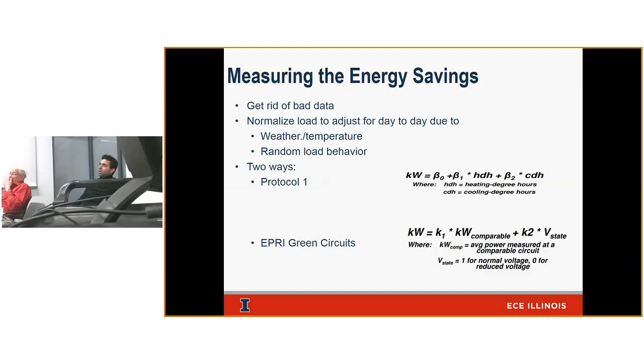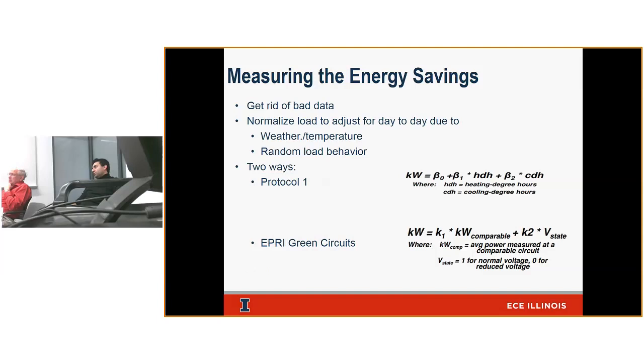These are the two main protocols used to measure VVO savings. First, get rid of bad data — zeros, missing voltage information, communication failures. Then normalize for day-to-day changes in weather, temperature, and random load behaviors. Protocol One uses a basic linear regression with coefficients for heating degree hours and cooling degree hours, since these are the most impactful to your load. I looked at a feeder with 8,760 hours of data and got every hour of temperature data from a nearby airport — a correlation of 0.98 between temperature and measured megawatts on the feeder.